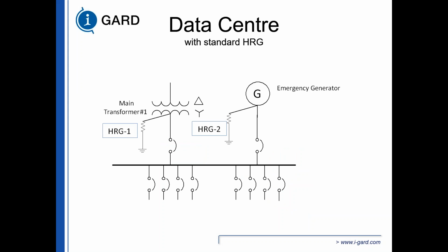So for a data center with standard HRG, typical data centers have a transformer and a generator. There's usually no tiebreaker in between these two because you're either on the transformer, and if you lose your power, you're on the generator, but you're picking up the same load. So basically, these two breakers are interlocked so that only one of them is on at one time. When you have a data center with high resistance grounding, what's going to happen is you're going to have a ground fault. And if you're on utility, this HRG system is going to tell you when you have the fault. And when you're on generation, this HRG system is going to tell you when you have the fault, because we're looking at the current going through the resistor here, or the current going through this resistor here when you're on generation.